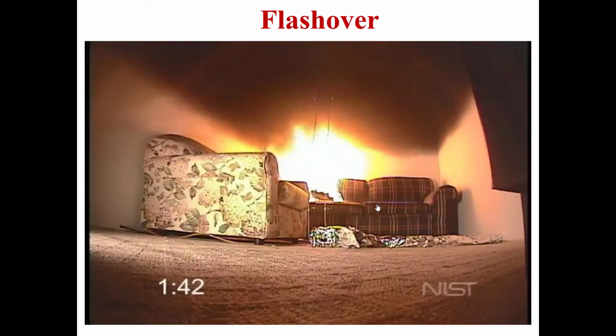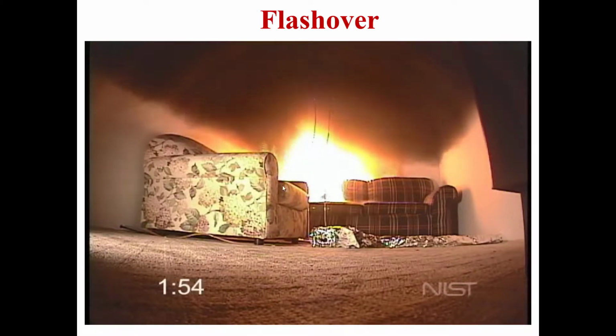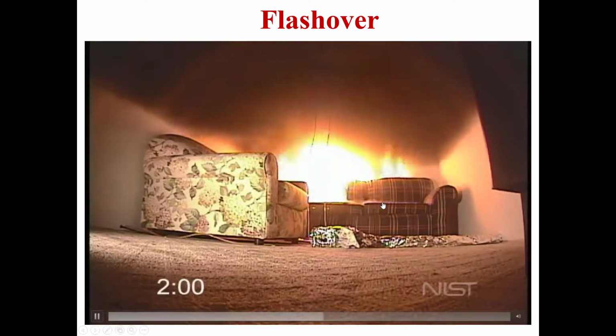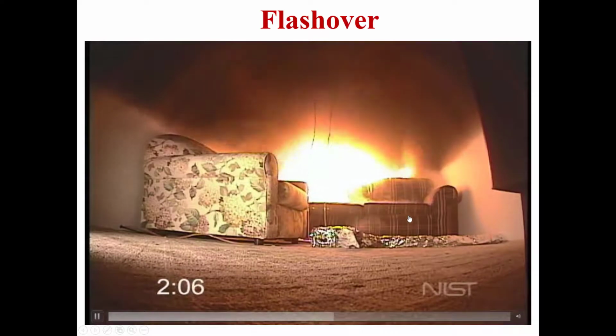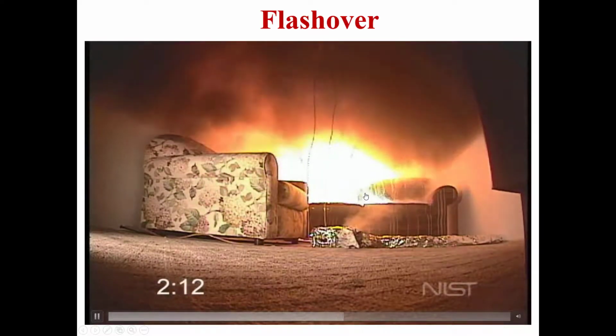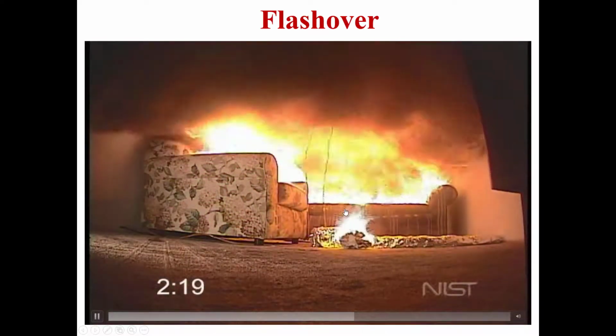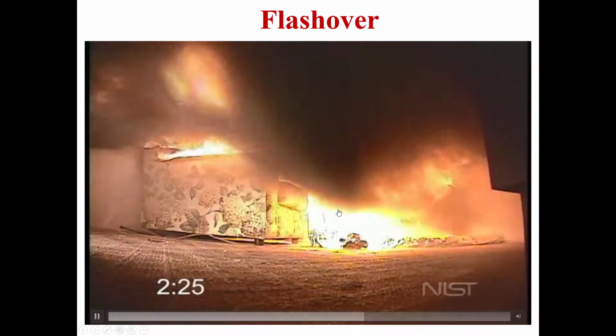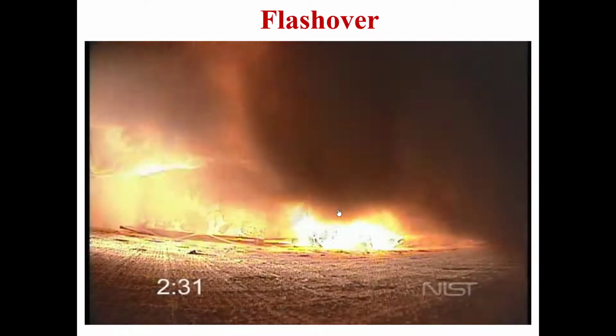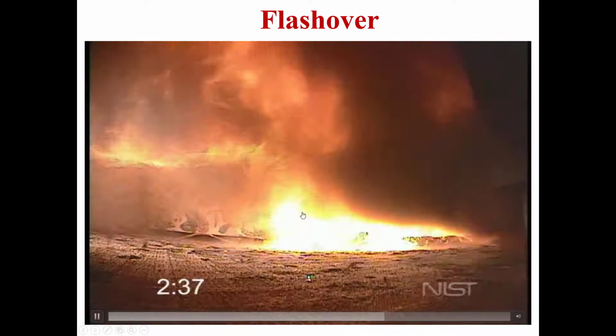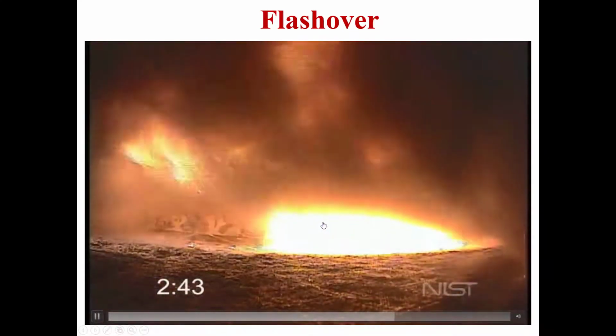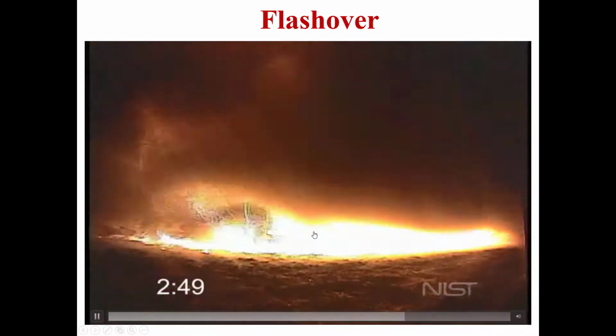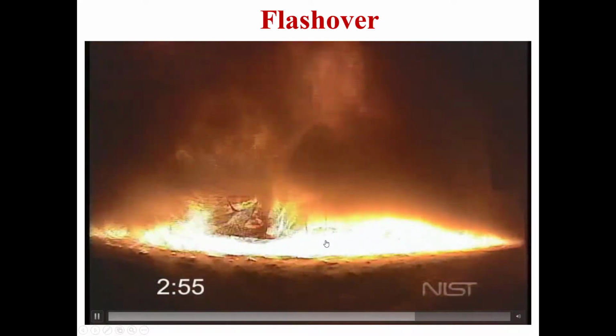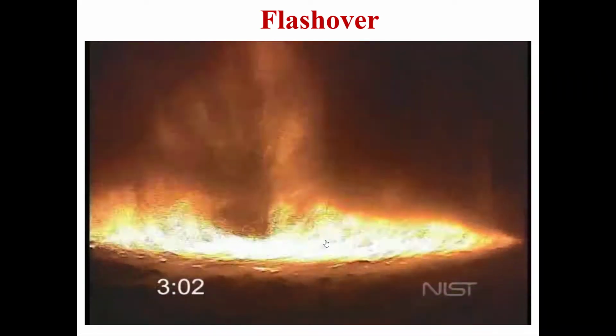Notice how within an enclosed space how fast this room becomes untenable. So there's the pyrolysis that I mentioned, the off-gassing of the solids. Very quickly the couches and chair get consumed in fire, and now we're proceeding rapidly to flashover. See the intake of fresh air from outside the room. It's also drawing some smoke back into the room. And we go to a flashover in under 3 minutes.